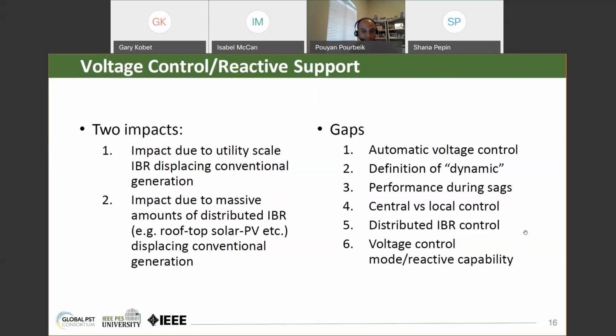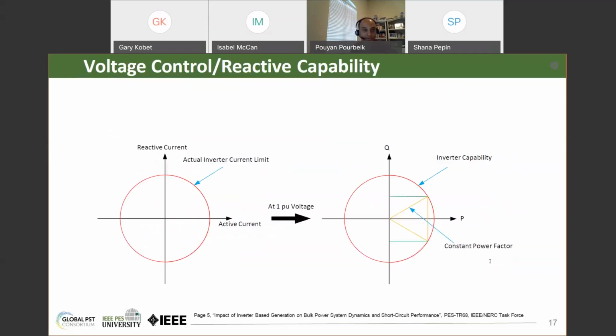If we go to the next slide, one of the other issues around this whole control of voltage and reactive power was this issue here. On the left-hand side, you see a simple diagram. It's showing you that an inverter or a power electronic converter is basically a current-limited device. So if we think about the y-axis being reactive current and the x-axis being active current, then it's just a circle on this XY plot. And obviously, the right-hand side of the circle is when you're putting active power into the grid, so like a wind plant or a PV plant. The left-hand side is if you have a battery, you can also absorb power from the grid. But it's essentially a circle.